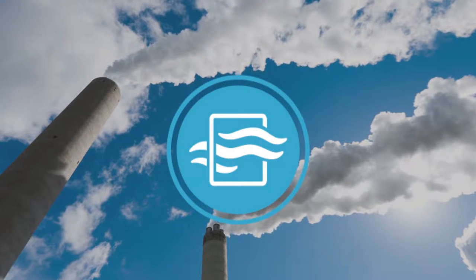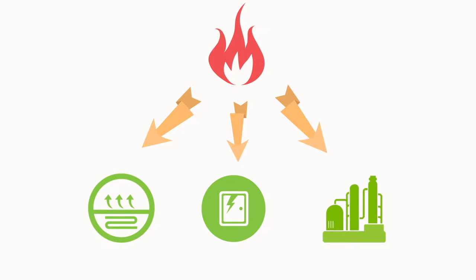When ambient air is preheated to 400 degrees, it gains energy and gives a hotter flame above 2,000 degrees. This hotter flame gives more radiative heat, faster heating, and more production.